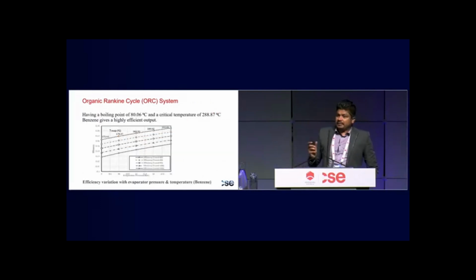I selected benzene as the best refrigerant option here, because it has a boiling point of 80.06 degrees Celsius and a critical temperature of 288.87 degrees Celsius. It gives high efficient output at different temperatures of 85, 90, 95, as you can see in this graph. 85 degrees Celsius would be the best operating temperature for this ORC system, since the boiling point is 80.06.